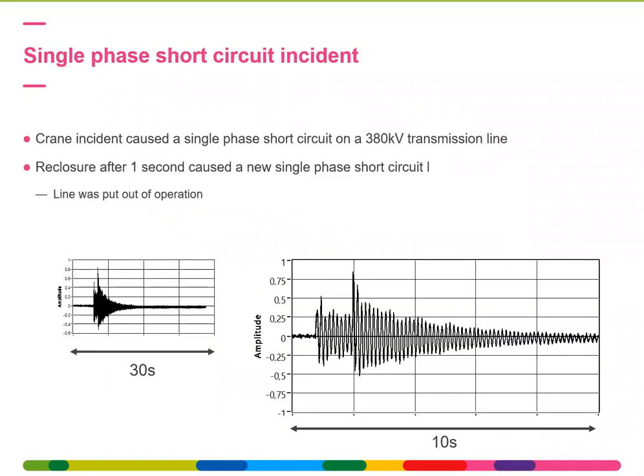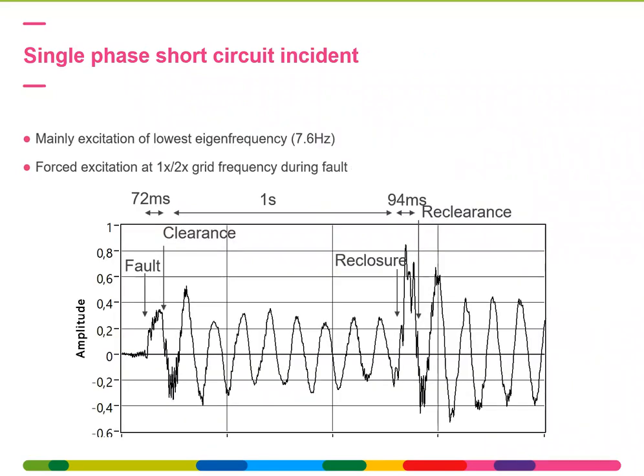I will skip these ones. Here is another example of a short circuit incident where a crane was too close to a transmission line and caused a single phase short circuit on a 380 kilovolt transmission line, which excites mechanically the shaft line. You can see the event lasts more or less 10 seconds. If you go more into detail here, this shows you the amplitudes again of the twisting angle in between both shaft ends. It goes in the order of 0.5 degrees.